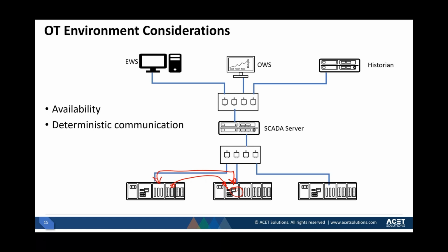And depending upon the criticality of the data, the second PLC may have a timeout programmed that if you stop receiving data from PLC 1, shut down the plant. And this is not just a hypothetical example that I'm giving. I've actually seen or worked in facilities where such programming was done, that if the communication is not received for X seconds, usually 1 to 2 seconds, this PLC will say, hey, my neighbor is not talking to me, and it may result in some unwanted condition in the plant, so I will shut down the plant.